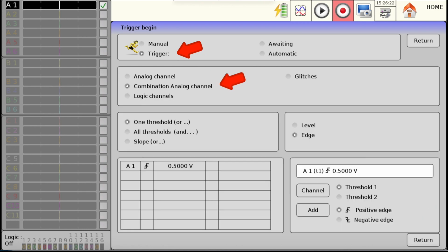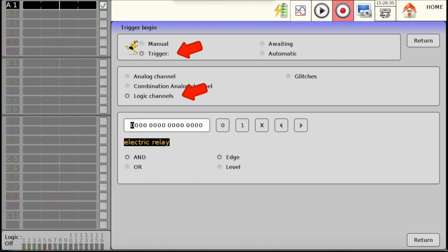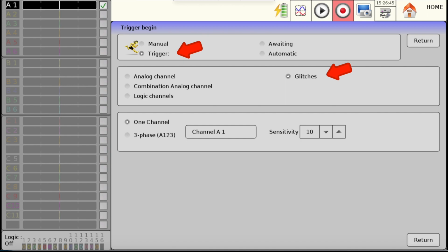The combination analog channel trigger will wait for the condition defined on the analog channel selected to be achieved. The logic channels trigger will wait for the condition defined on the logic channel selected to be achieved. Status is changed to 1. Glitches trigger is dedicated to the recording when glitches appeared on signals.